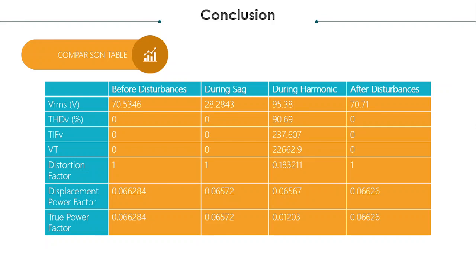And while the displacement power factor remains the same even with the presence of harmonics, the true power factor gets smaller as harmonics are added and becomes less than the displacement factor. Both TPF and DPF are equal in non-harmonic situations.